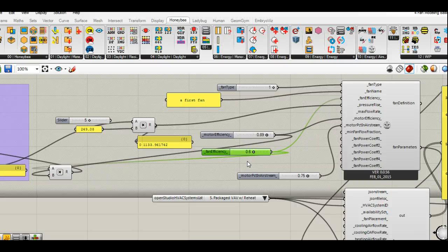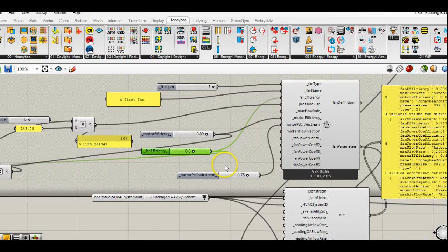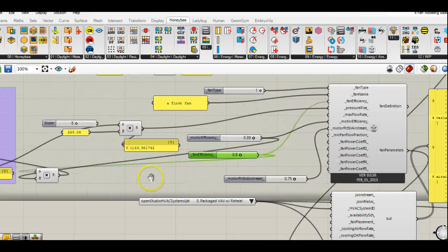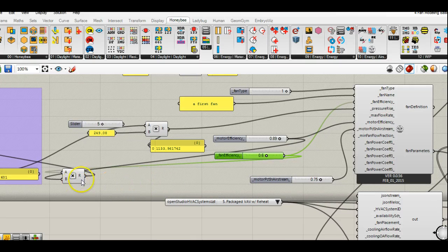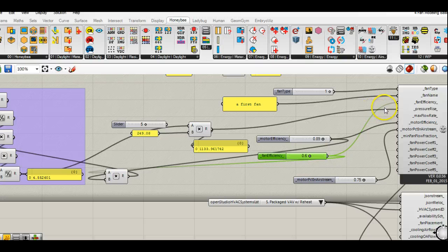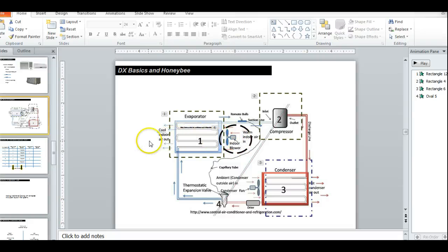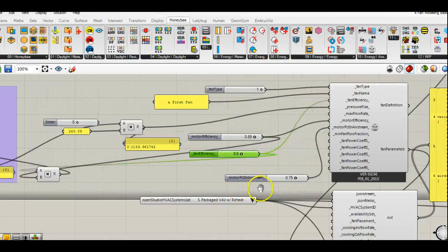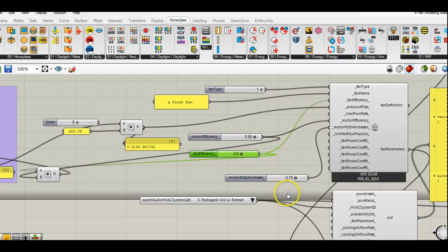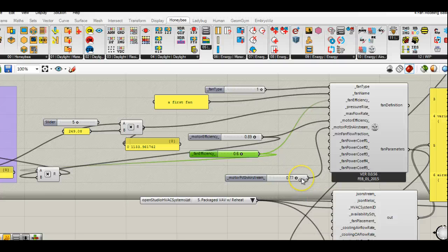One final note I'll make is that because you're only specifying a single fan, if you want to really be picky, you're basically plugging in enough power here to power both the supply fan and the return fan. But it all ends up in OpenStudio right here blowing across the coil. The fan is going to add heat to the system, so if you want to be fair and take some of that heat out you can. I think that's a little bit of an esoteric exercise. I usually don't use that value.